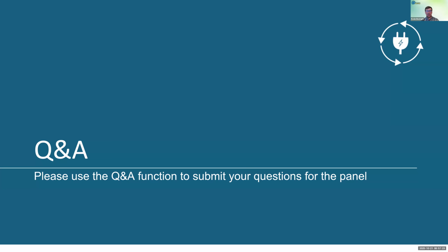That's a really good question, Christina, because a lot of times the way these are set up, they come across as an engineer's tool rather than a facility operator's tool, because there's so much data. The promise is that you look at these faults and the system directs you toward the potential cause, like a root cause analysis. But that's the promise, it doesn't always end up that way. So you end up with all these errors and faults, and you go, what is truly causing this? That's the difficult part. It takes a lot of forethought into how the system is designed, understanding if you're getting a fault here, what are the potential causes. That involves the design team heavily, helping whoever implements the FDD system understand how it works and where the causation could be coming from. It's a really difficult process to do right.